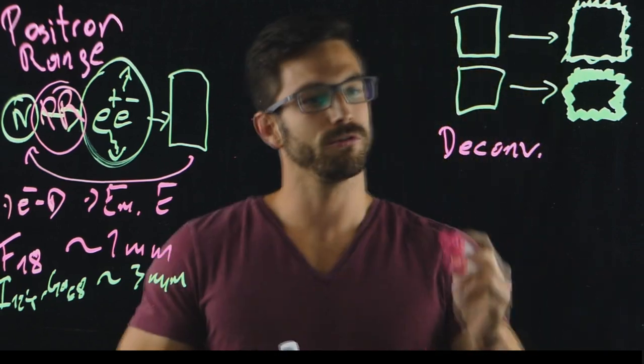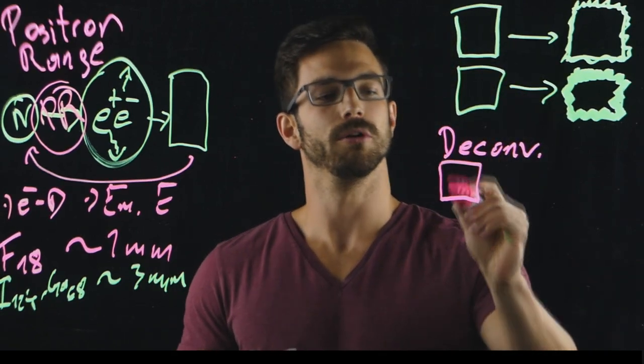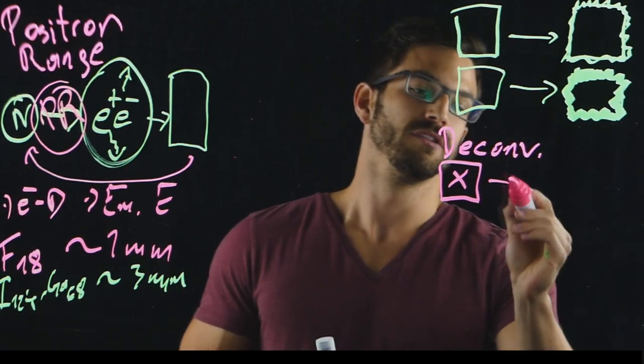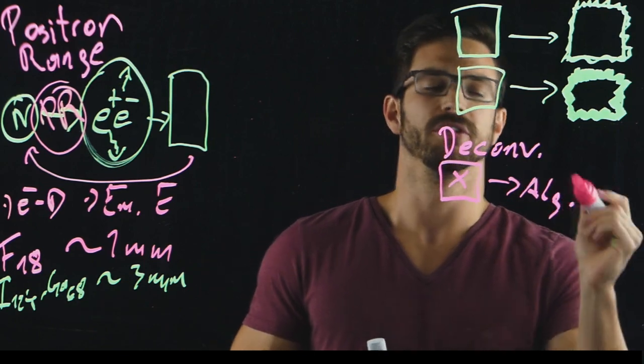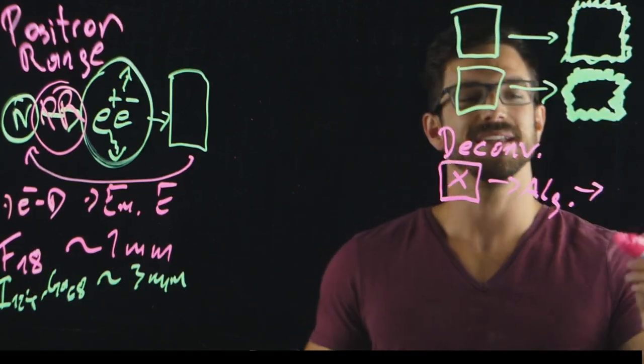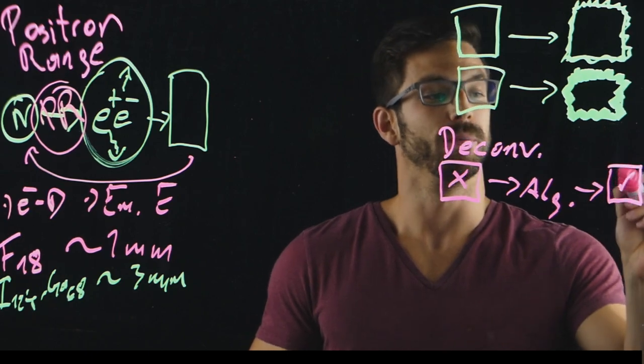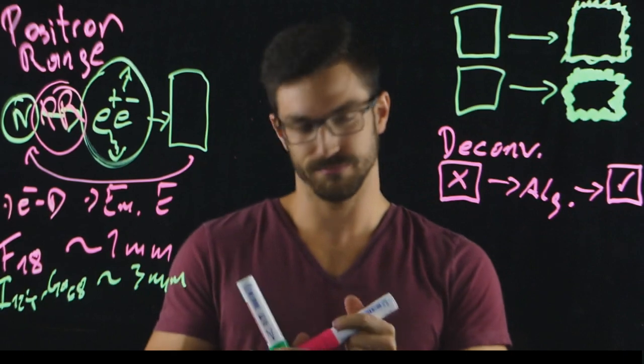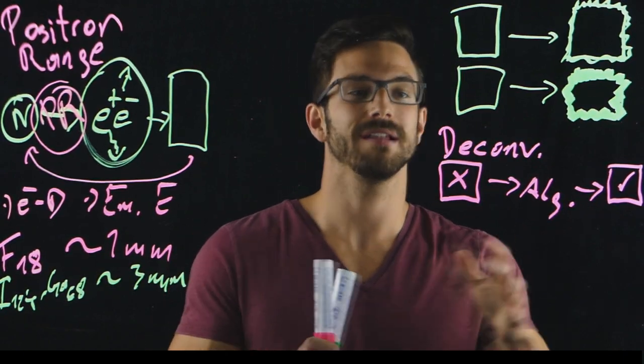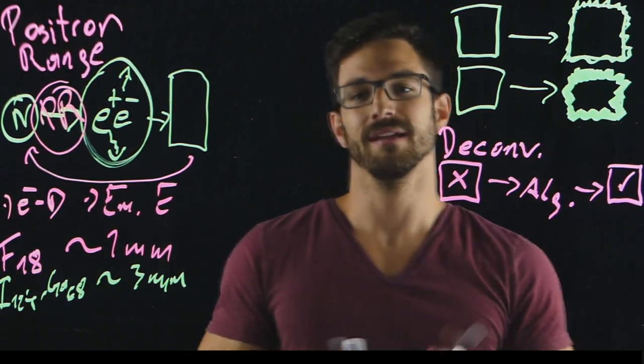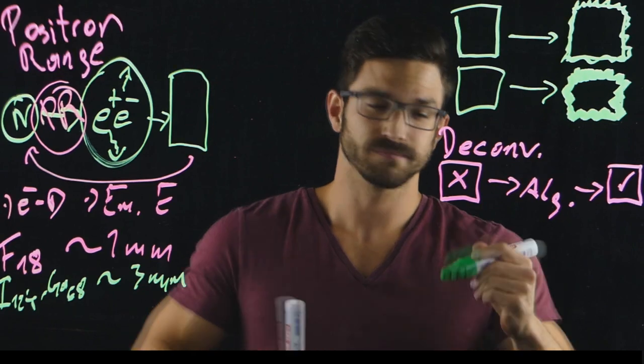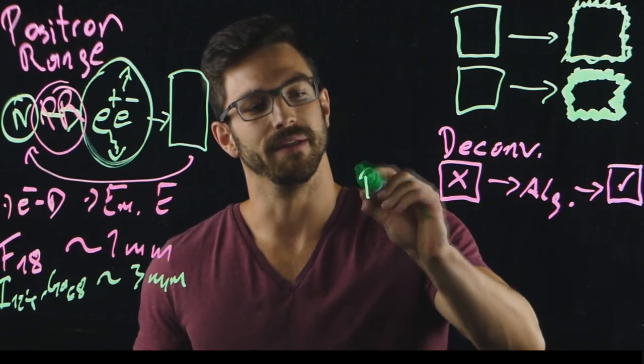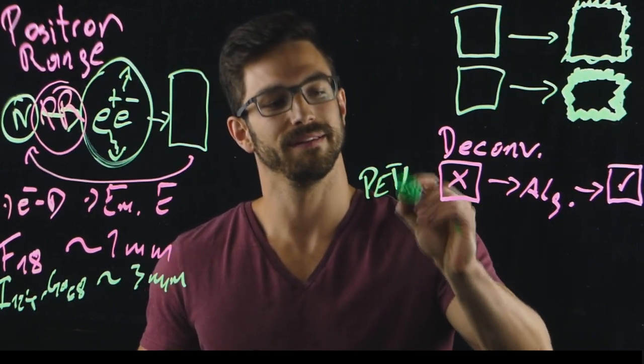What we do in deconvolution is that we take the blurred image, use an algorithm as a post-reconstruction technique, and what we get out after this is an image that is corrected for positron range. A little bit of noise is induced by the deconvolution algorithm. Nevertheless, it deals with the blurring. This is standardly implemented in PET-CT.